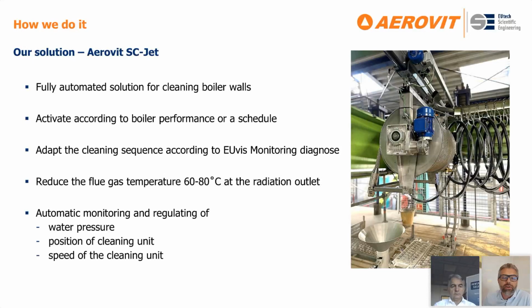So you don't end up cleaning areas that are already clean, but you focus on the areas where you have the fouling on the panel walls. So if you do it correctly, you can actually reduce the flue gas temperature at the radiation outlet by about 60 to 80 Celsius degrees. And therefore you have a better performance boiler, and you don't have the melting particles on your superheater. So basically it ends up with having a more well-performing boiler, but also less stoppage for manual cleanings.